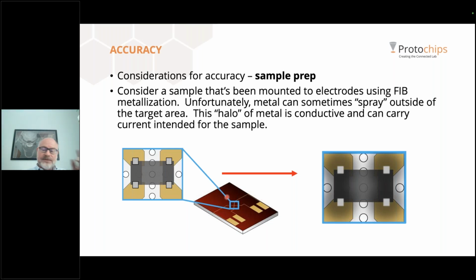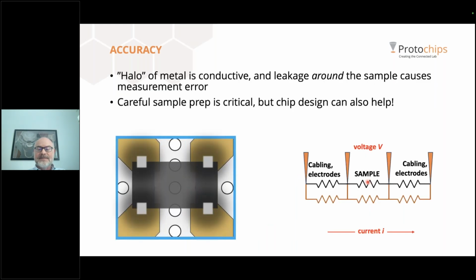Another, perhaps more important consideration is sample prep. Every sample requires some form of sample prep, and sometimes the prep itself can cause problems. For example, consider a FIB lamella that needs to be electrically connected to an E-chip. Now, one advantage of FIB is that in addition to cutting and thinning the sample, you can deposit metal onto it to form electrical connections. However, when you're trying to form several contacts within a small area, any stray metallization, like a thin halo of metal, can form electrical connections between the contacts and around the sample. So the key here is to avoid the overspray of metal that can lead to current paths around the sample and confuse your measurements. People have reported that tungsten is sometimes preferred to platinum because it has less overspray.